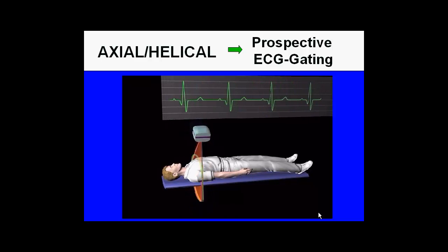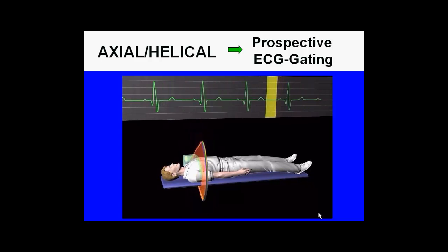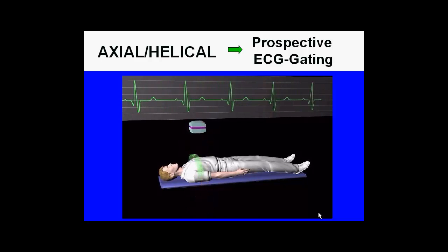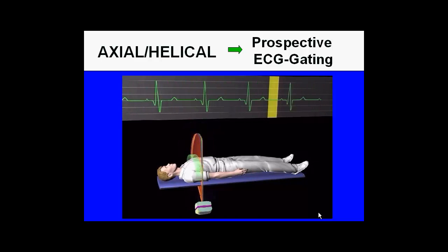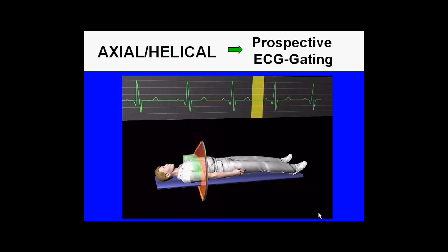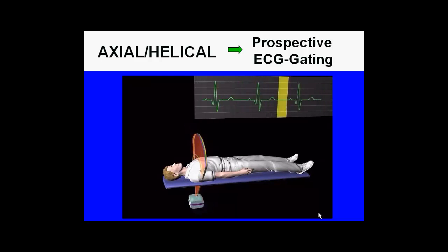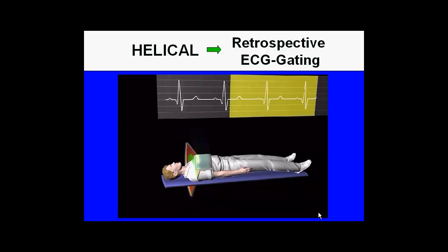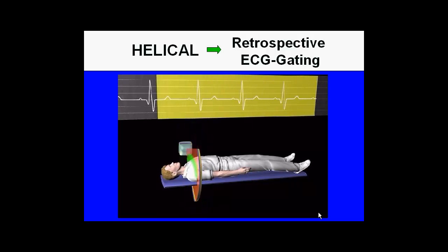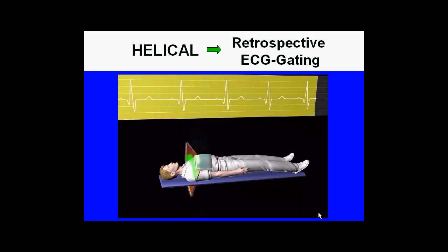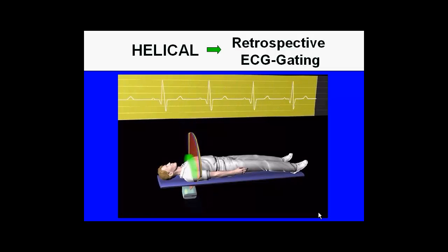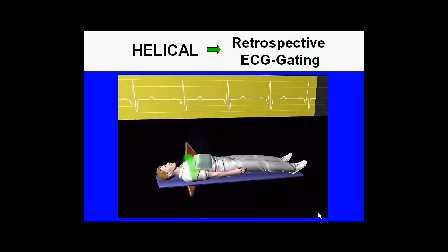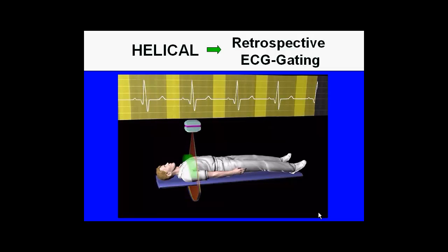For cardiac imaging, you can do prospective ECG gating, which basically turns on the camera only at a certain time during the cardiac cycle. This significantly reduces radiation exposure and is done either in an axial or step-and-shoot axial manner. The other method is retrospective ECG gating, where the camera is on the entire time as the patient table is moving to acquire spiral-like images. This produces the most radiation but also provides the most data for retrospective reanalysis.